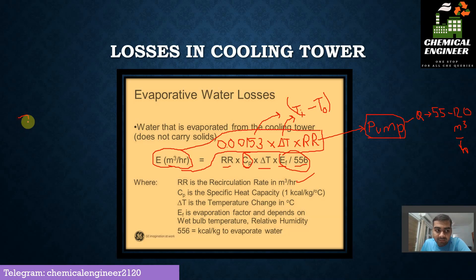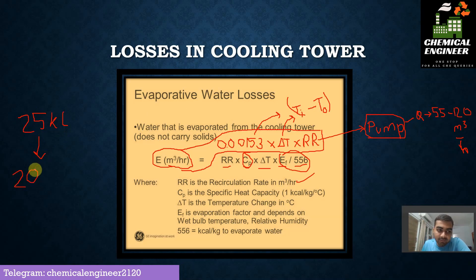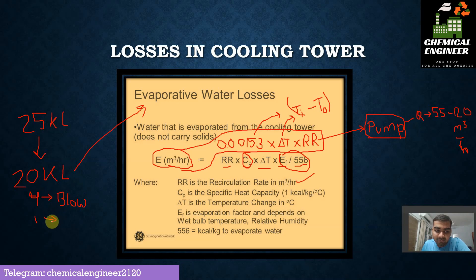For example, suppose 25 kiloliters of water are added to your cooling tower in one day. Of that total, around 20 kiloliters will be lost through evaporative losses, about 4 kiloliters through blowdown based on water quality (which we will see in the next video), and around 1 kiloliter from other losses. That is all about evaporative water loss calculation. If you have any doubts, please comment below or ask in the Telegram group. Thank you for watching.